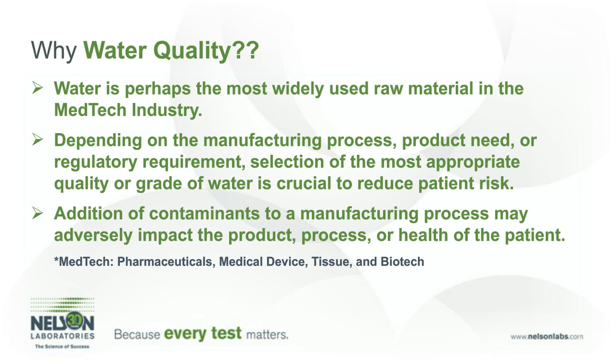When we use the term water quality in the medical device industry, we are typically referring to water quality or purity of water greater than that of potable or drinking water from a municipal source. The quality of water is dependent on the manufacturing process, product need, and regulatory requirements. Contaminants such as bacterial endotoxin, microbial contamination, and particulates from water of lesser quality used in the cleaning process may significantly impact the health of the patient, the functionality of the device, or the performance of the manufacturing process.